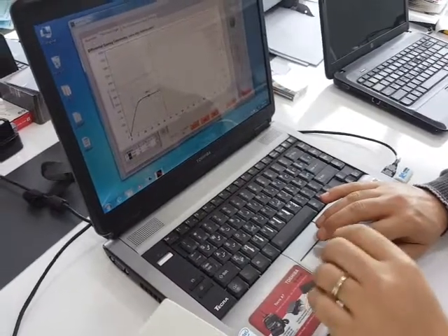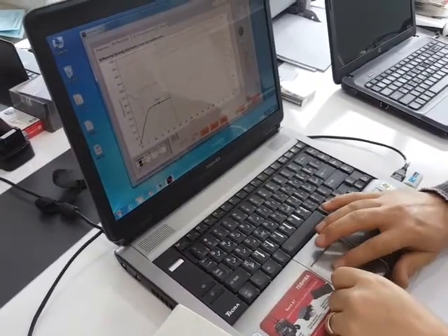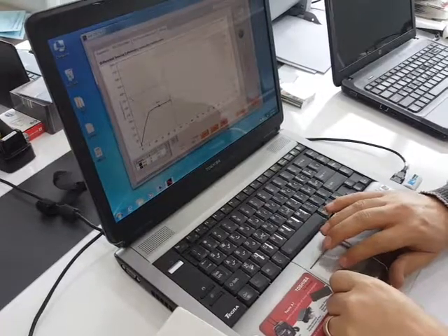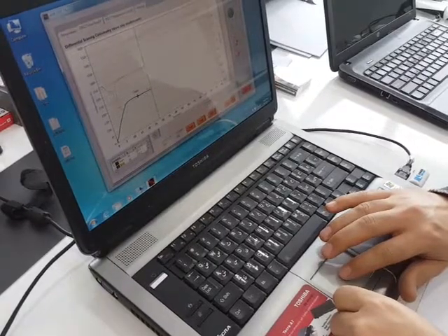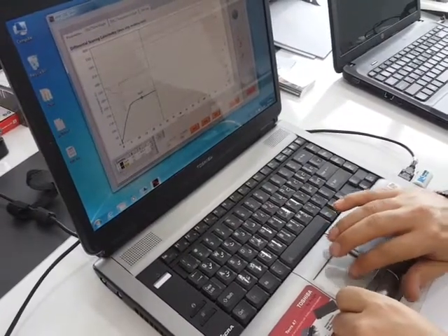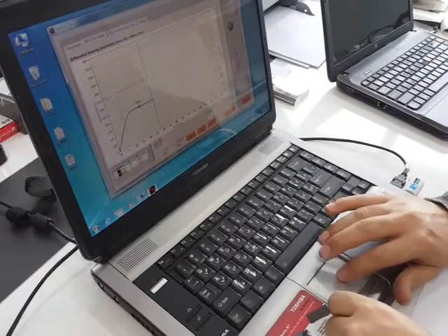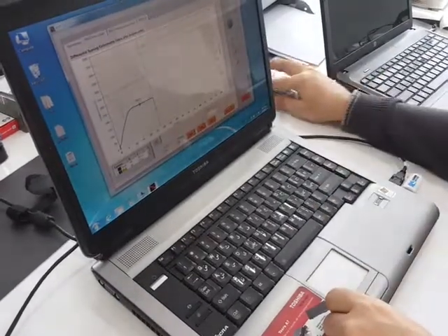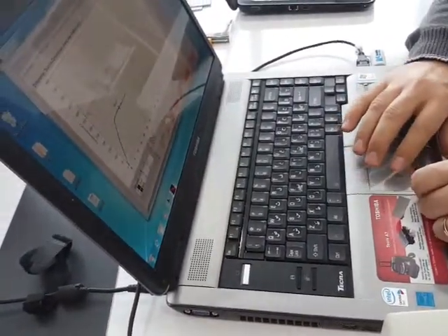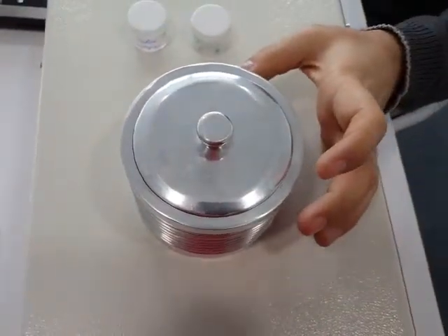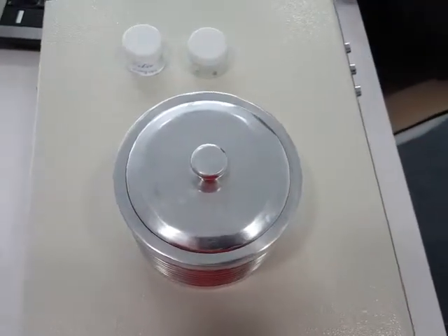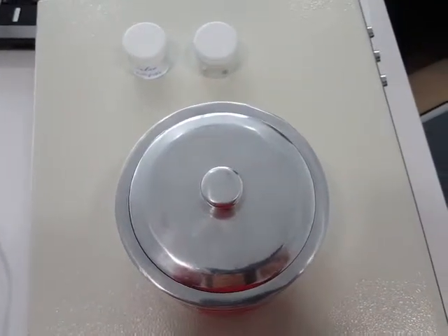If the oxygen doesn't input to the chamber, the material will not be degraded. I mean, the operator will see the melting point, but it will not be degraded. I mean, the break point of the sample will not be shown in the DSC graph. For checking if the oxygen is coming to the chamber or not, the operator can manually open the oxygen valve.